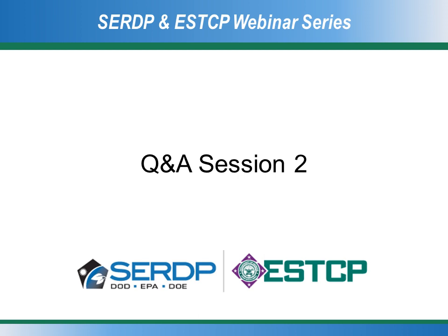I am, sorry. Yep, I guess there's twofold I mentioned. One is for ongoing metering at facilities. One of the biggest concerns with metering programs is really the quality analysis of the data, making sure that any bad data is captured and found. So one of the best ways of doing that is to be able to integrate existing meter data into a single system, as well as being able to install key sub-meters or other duplicate meters at key facilities and integrate those and be able to get software to automatically start looking for issues. So for example, if you have one full building meter and several sub-meters, the system can sum up the sub-meters and check that against the whole building meter to look for any issues there. So there's a lot more QA you can do with an integrated system such as our MeterManager system.